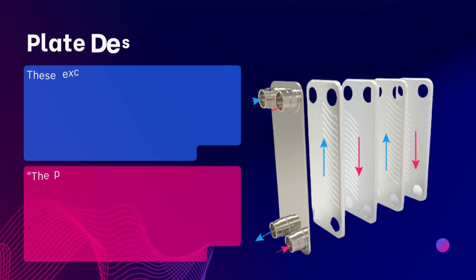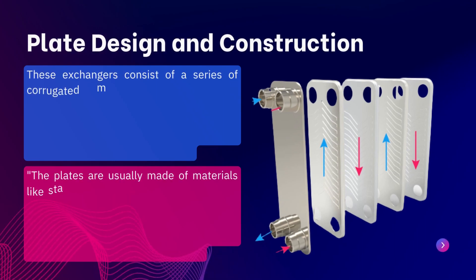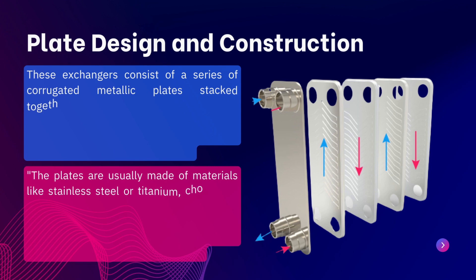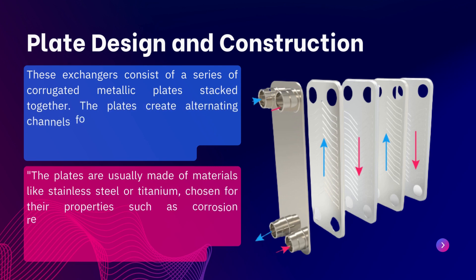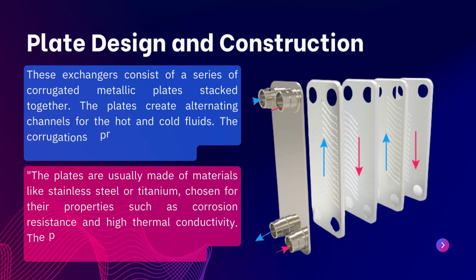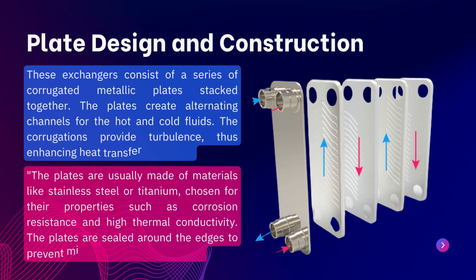Looking at the design and construction of a plate heat exchanger, as we can see in the figure, it consists of a series of corrugated metallic plates stacked together. Alternating channels are created for hot fluid and cold fluid. Turbulence is created through the corrugations, which increases heat transfer efficiency. The plates are generally made of stainless steel or titanium, selected for their corrosion resistance and high thermal conductivity. The plates are sealed around the edges to prevent leakage and fluid mixing.